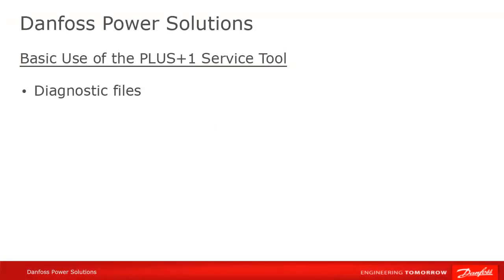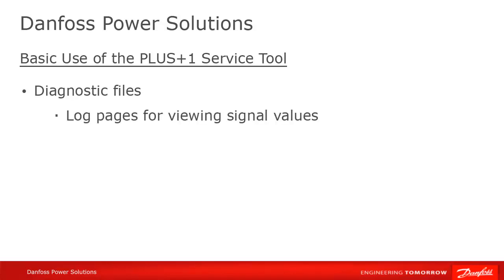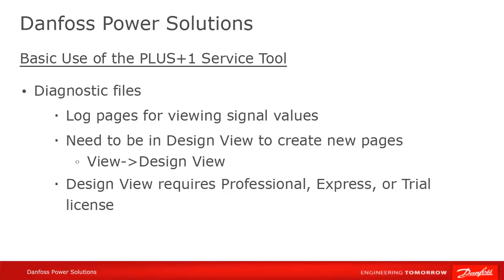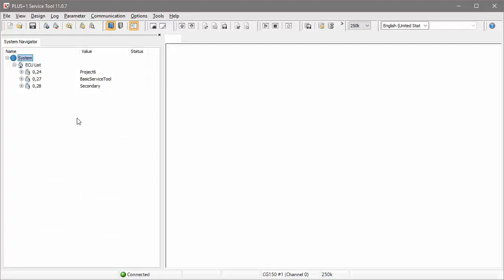After download, the service tool is also used to view what's going on in your program on the controller or display. You can do this on log pages. To create a log page, you first have to verify that you're in Design mode. Select Design Mode in the View menu. If it's grayed out, you might be using an unlicensed version of the service tool. You need an Express or Professional license for the service tool in order to create new pages.